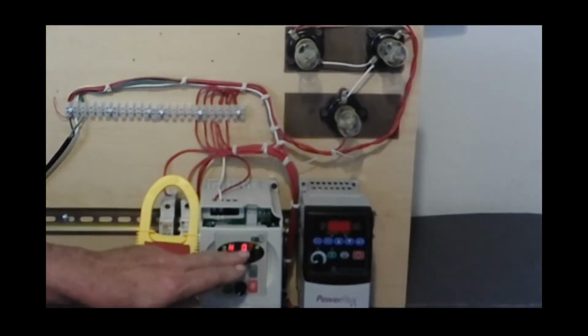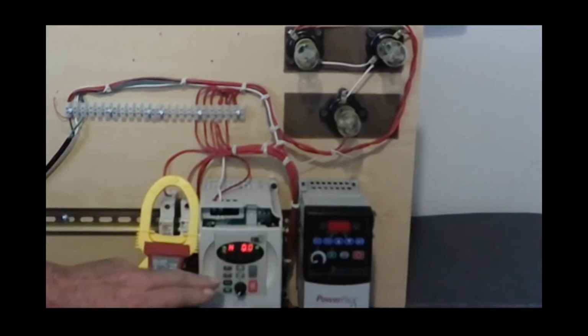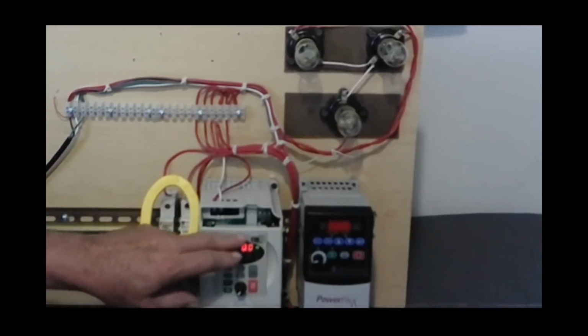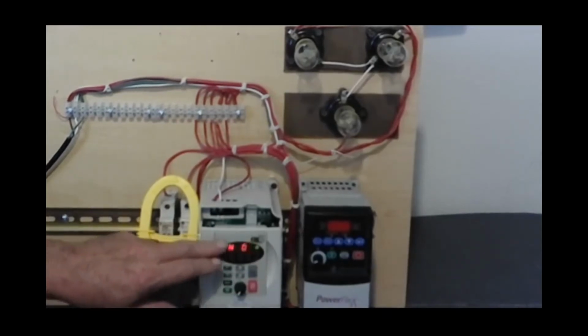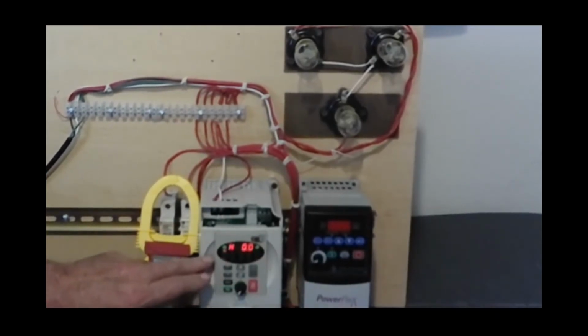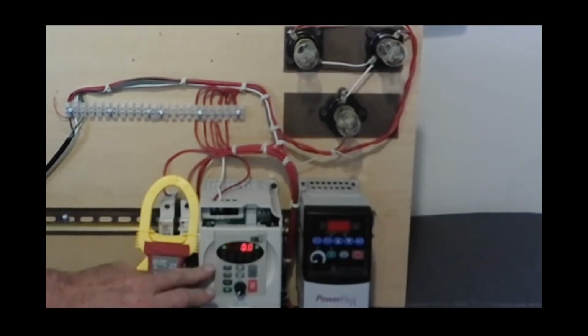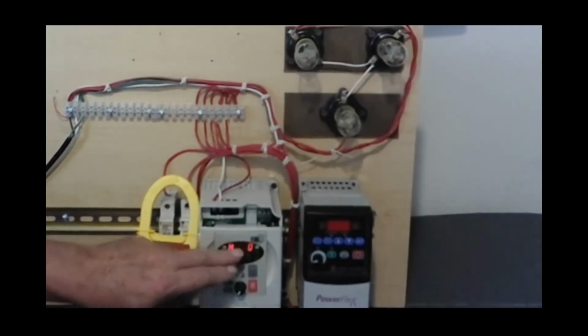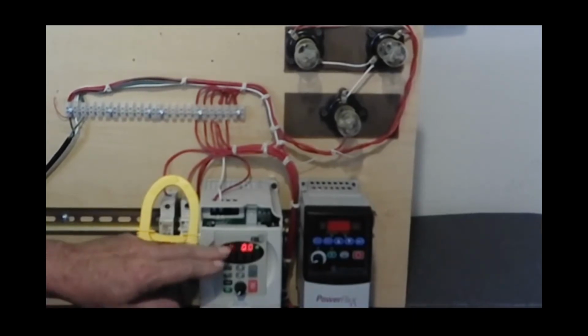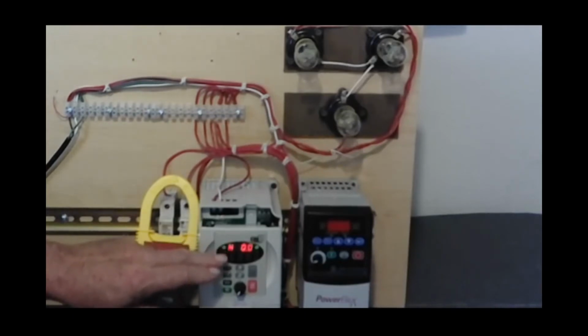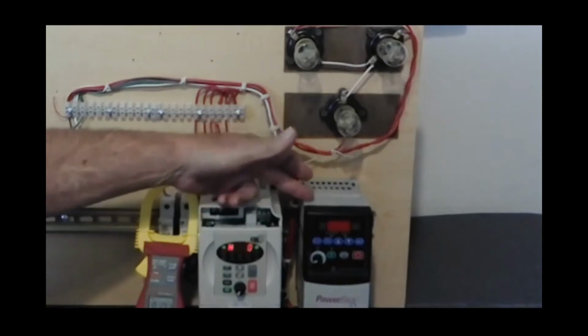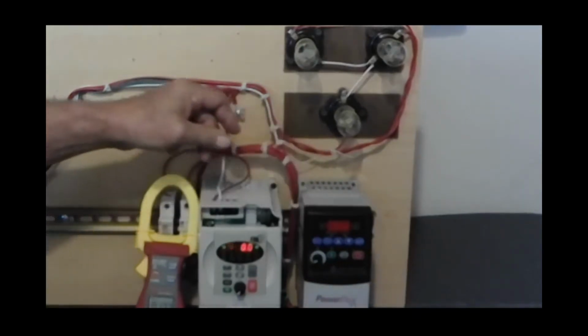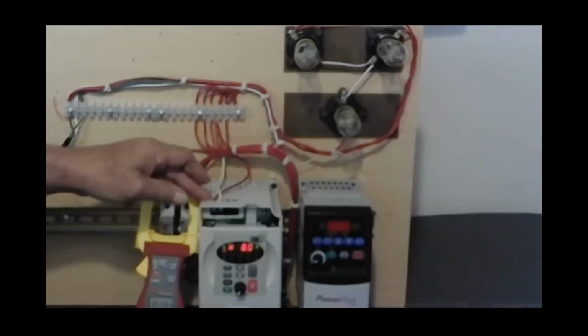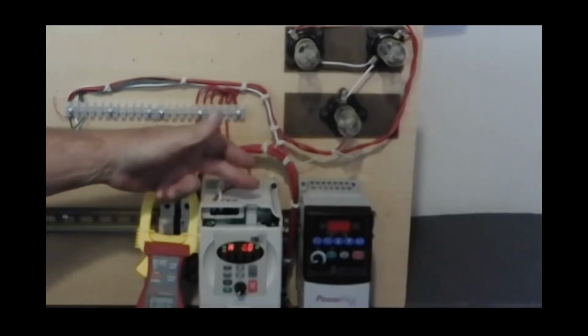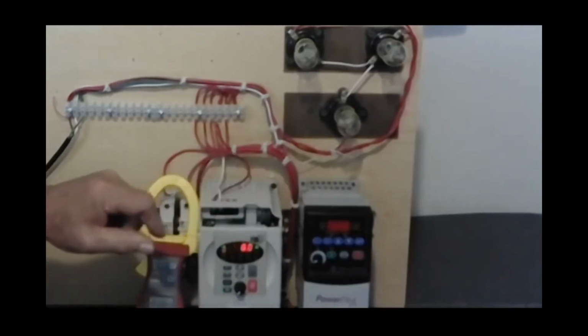My point being, if this screen or this screen will light up, you can troubleshoot the drive. If there's something internally wrong, you can go through that little menu right here and troubleshoot internally in the drive. But it's going to come up with a set of codes. Now the problem here is, without that printout or that original manual, you don't know what the codes are. Some of the drives, like the AB, will have a list of codes printed on the side. Others will not. So the codes themselves are going to tell you what's wrong with only the one specific type.